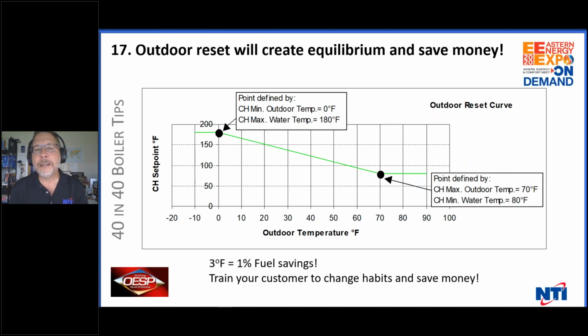Why am I putting 180 degree water into a system when it's 50 degrees out? Because we get our energy from oil or gas. We turn it into flame, still energy. We take that energy, now heat, transfer it into the water, still energy. We take that energy as heat and we take it out to the system through baseboard or radiant tubing or fin coils or convectors or radiators. It's all great, but we're trying to make up for the amount of heat going out of the house by putting more heat in. For the amount of energy going out, we need to put the energy in.